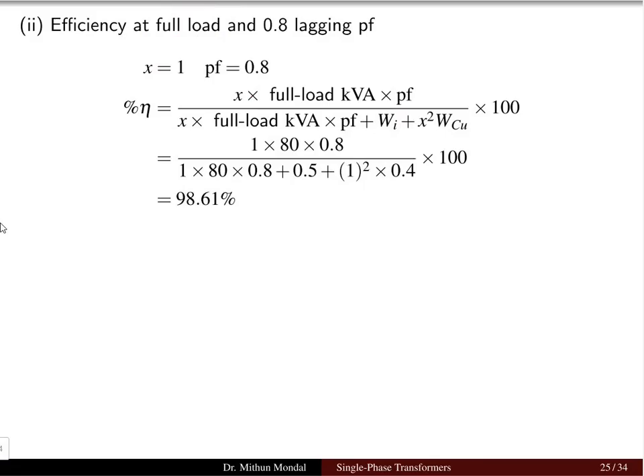So if the loading is X, obviously the power loss on the copper side we have to multiply by X squared, and iron loss is independent of the loading. So the first problem, where the full load is there and power factor is 0.8, we will get 98.61% efficiency. Transformers are the most highly efficient devices in the entire electrical machines. So here the efficiency will come more than 95 to 98%, which we will usually get in the problems. So here 98.61 we are getting under the full load.